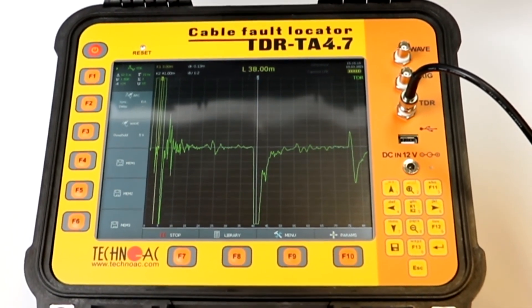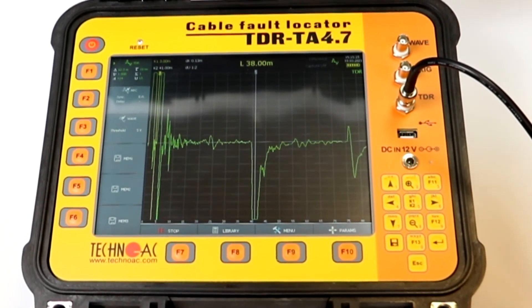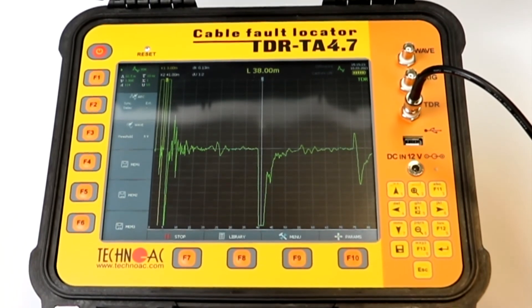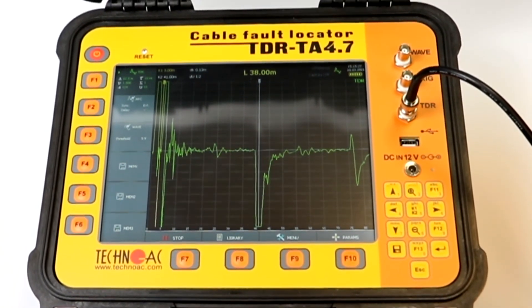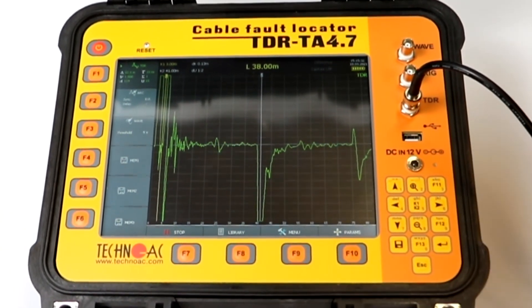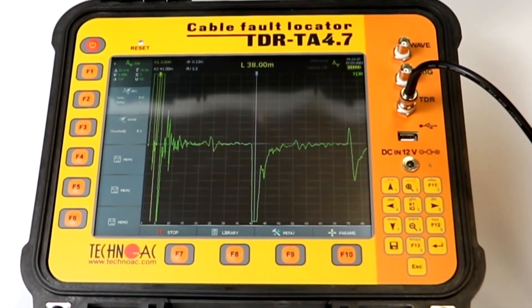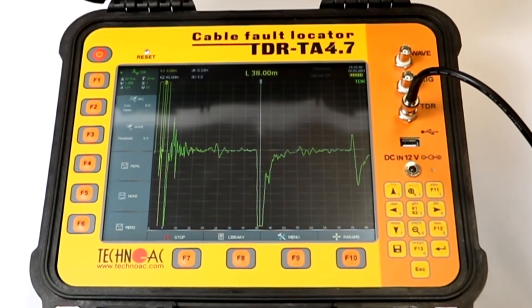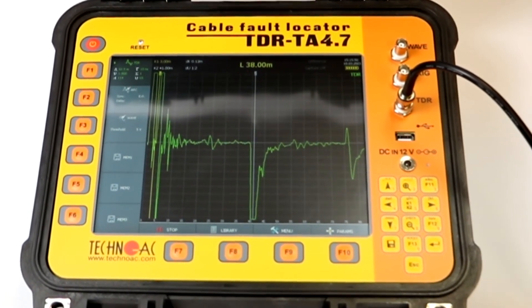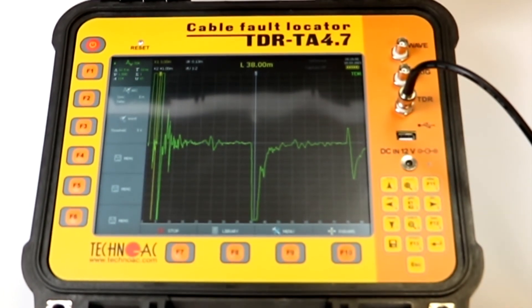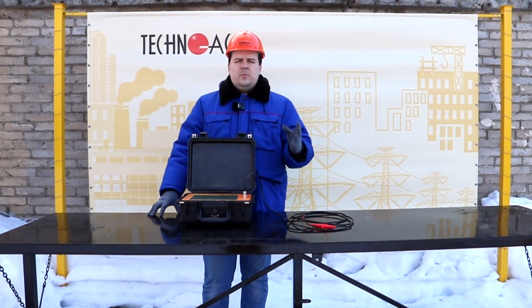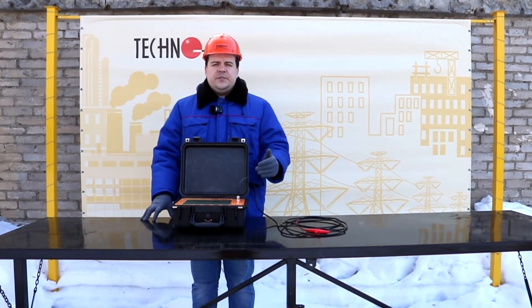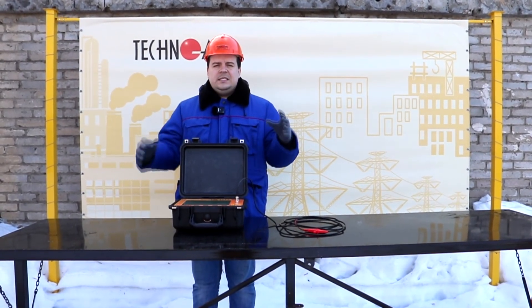Also, please note that the distance indicated by the device is not the real physical distance — it's electrical distance. So if the cable has coils or moves left or right, the distance will be indicated only as electrical distance. After measuring and indicating the fault, you can press the save button and save the measurement in device memory. Then, by using a USB flash drive, you can upload it to your local PC, create a test report for this particular measurement, and file the report to your client or manager.